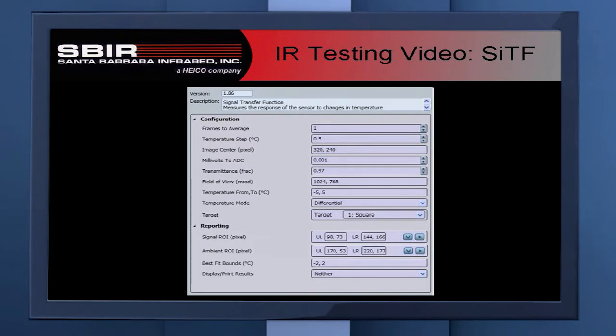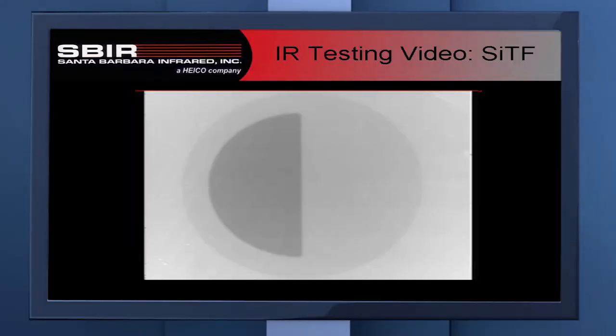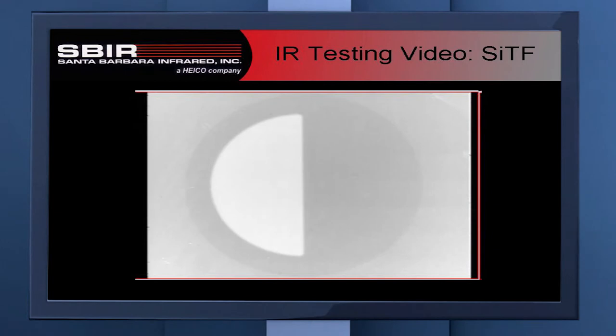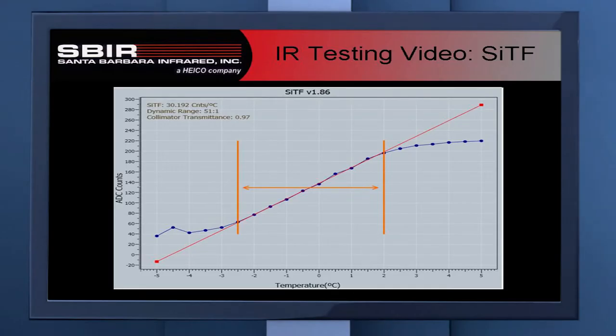For setting up this test, we define a set of range temperature measurements — going from say minus five to plus five differential temperature — in half-degree or tenth-degree increments, stepping through each temperature and taking measurements from the camera. At the first measurement the temperature is lower than the background so it appears dark. As we go up in temperature we see brighter and brighter images. There's a point where the background matches the blackbody so it looks like one big gray image, and finally we get to a higher temperature and the camera responds with a brighter image. We graph those measurements as an S-curve, where each point is a measurement taken from stimulating the camera and looking at its response.